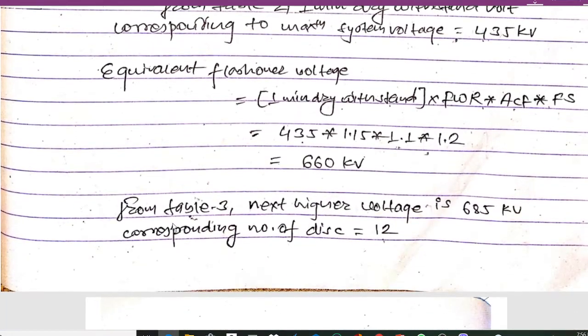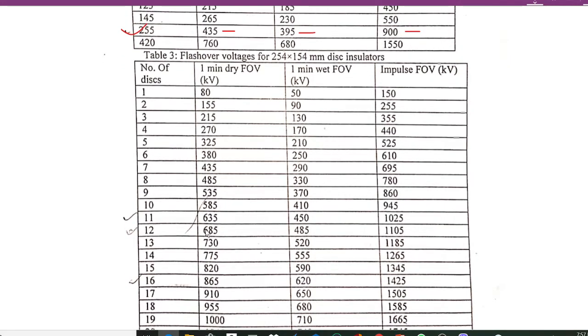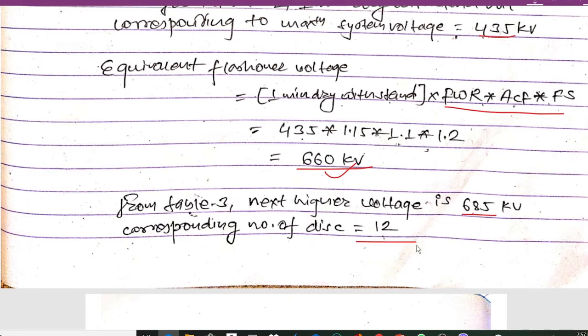The equivalent flashover voltage formula is: one-minute dry withstand standard × FWR × ACF × FS. Substituting 435 × 1.15 × 1.1 × 1.2, we get an equivalent flashover voltage of 660 kV. From Table 3, the next higher voltage above 660 kV is 685 kV, and the corresponding number of insulator discs is 12.